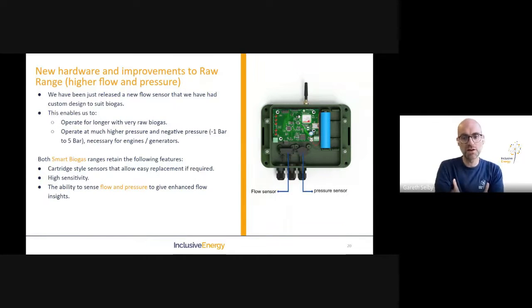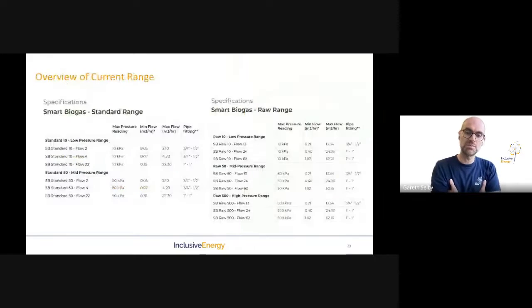With that, we currently have on both product ranges cartridge style sensors, which allow easy replacement if required. So as and when, if the worst happens and the sensor does fail, it's as easy as just pulling it out and plugging a new one in. We have great sensitivity, as I've mentioned before. And critically, we measure flow and pressure, which, as we'll come on to later when we look at analytics, is what really gives you great insights into the performance of the biogas digester.